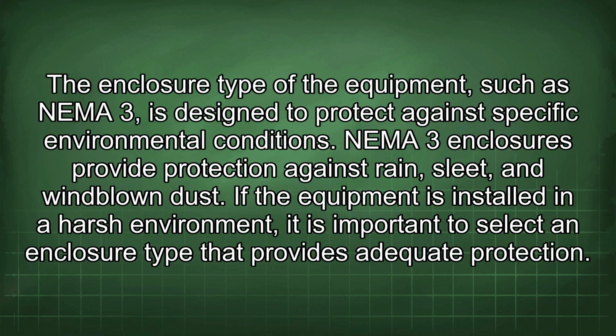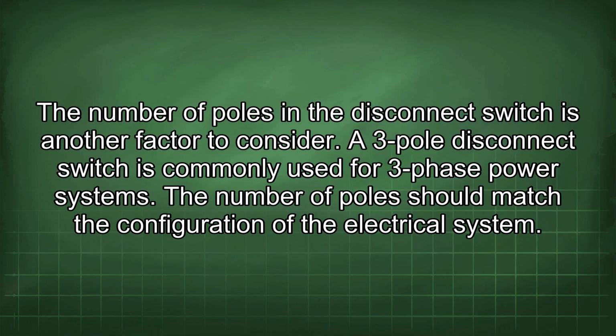The enclosure type of the equipment, such as NEMA 3, is designed to protect against specific environmental conditions. NEMA 3 enclosures provide protection against rain, sleet, and wind-blown dust. If the equipment is installed in a harsh environment, it is important to select an enclosure type that provides adequate protection. The number of poles in the disconnect switch is another factor to consider. A 3-pole disconnect switch is commonly used for 3-phase power systems. The number of poles should match the configuration of the electrical system.